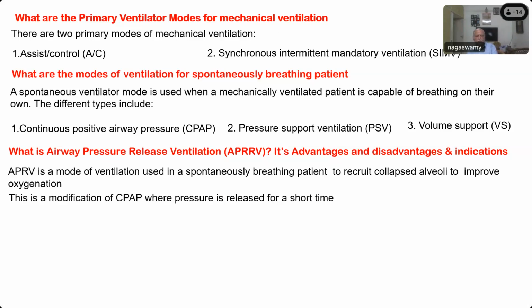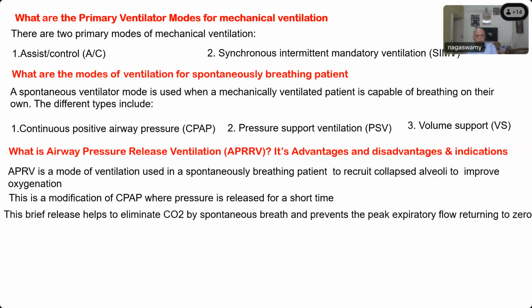In CPAP, it is constant. Supposing you set 7 centimeters pressure in a CPAP machine, that same 7 centimeters will be present both during inspiration and expiration. That is why it is called continuous positive airway pressure. Whereas if you temporarily, for a brief period, release that pressure and then re-establish it, that is called airway pressure release ventilation. This brief release helps to eliminate carbon dioxide by the spontaneous breath of the patient and prevents the peak expiratory flow returning to 0. It will always be a little higher than 0, so the next breath can be easily initiated.